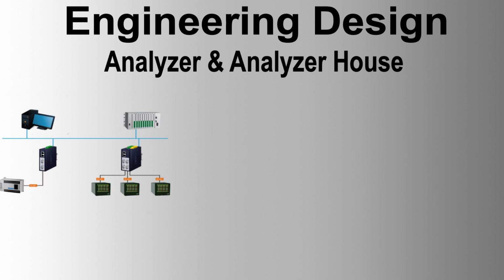Space, the sample handling area, should be reserved on the outside walls of the analyzer house for the installation of sample conditioning systems, and should allow the analyzers and sample conditioning systems to be installed back to back. The length and height of this sample handling area should be the same as that of the analyzer house. The unobstructed walk space should be a minimum of 750 millimeters. The degree of weather protection of the sample handling area depends on local conditions and the required condition inside, but should include at least a canopy.